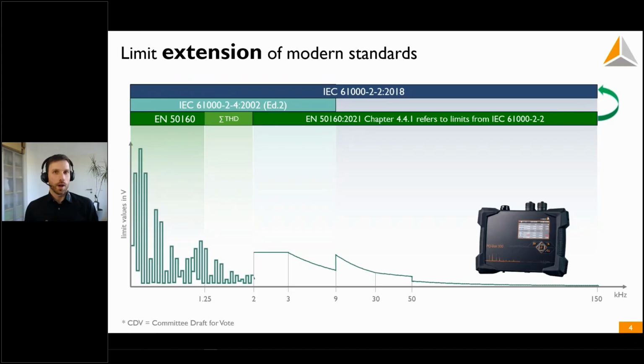The widespread EN 50160 in Europe got a similar approach. They extended not their own limit values, but they said that if you experience interferences in the high frequency range, we do not have our own limit values, but please have a look at the IEC 61000-2-2. This is the IEC EMC standard for public grids, and this covers the frequency range up to 150 kilohertz. So the EN 50160 from 2021 refers to the limit values from the IEC standard.